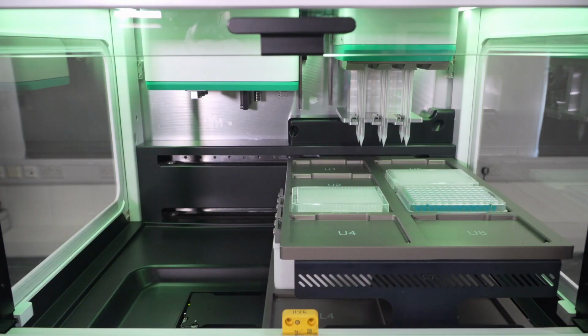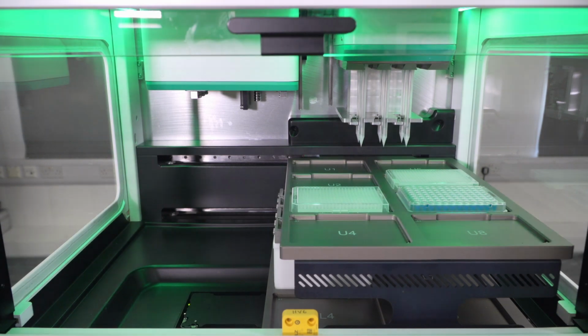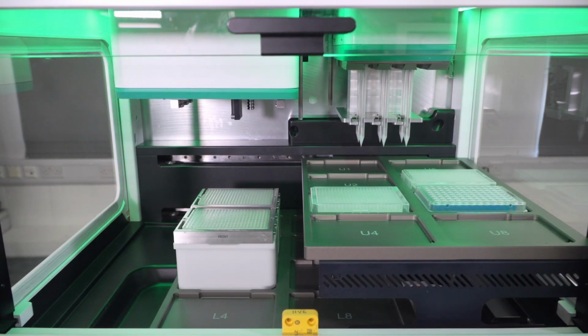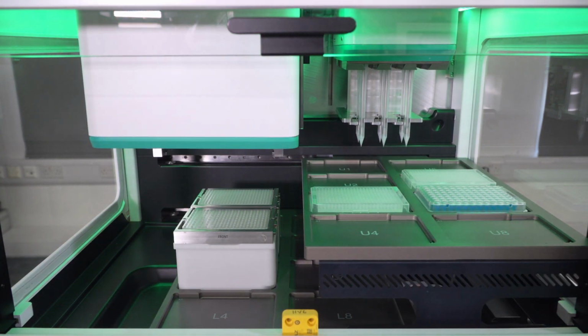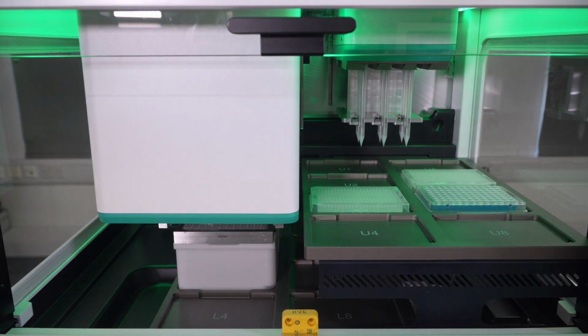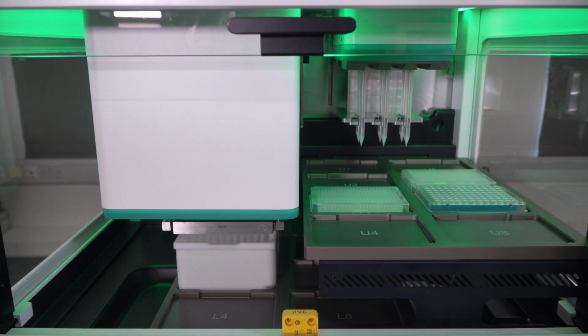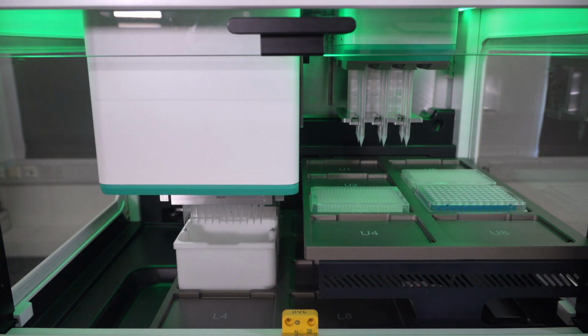Right, so I'm going to hit play now and start this protocol. First it's going to pick up a set of 96 tips. So it's just loading those onto the head now. It can switch seamlessly between different tip formats during a protocol, just as part of standard programming. So it's very flexible in that respect.